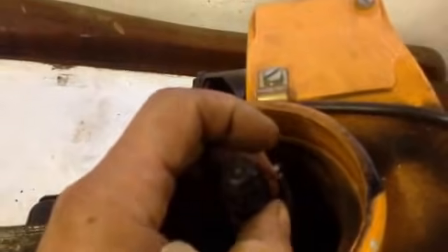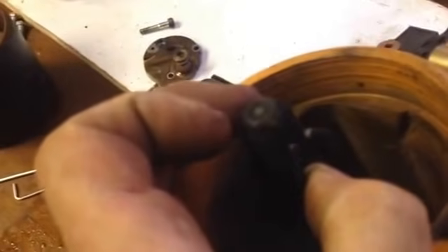Okay, so you're in the blast tube. If you hear that spark, you hear the click as it lets the diesel through, and then you don't hear it light, it's possible that these igniters are not functioning. Now what you can do is get in and look, and you can see if they've got a gap - because sometimes these will split too far apart. By distance you're talking - this is a hell of a spark on these things, so there's such a difference.